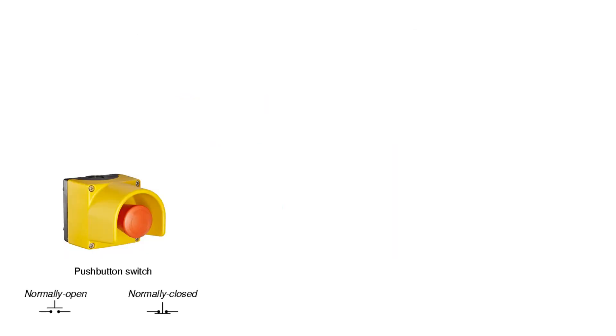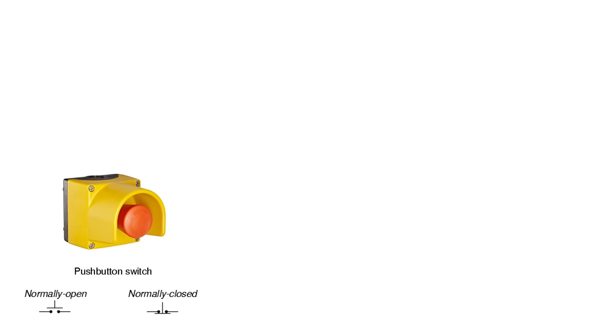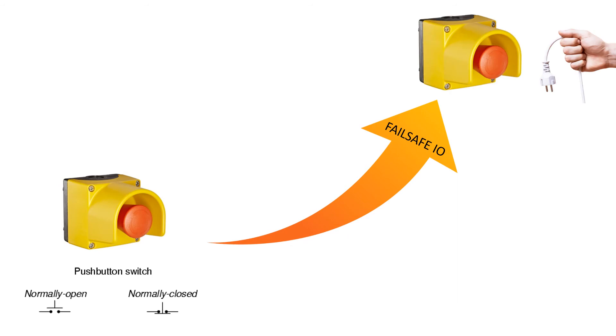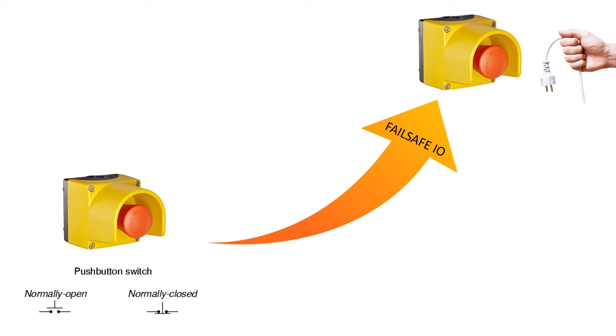Safety IO devices are typically wired in a normally closed contact arrangement. That means the contacts on the e-stop shown here are normally connected. The signal coming back is normally on until the button is pushed. The reason for this is so that if a wire gets loose or disconnected, the control system will shut down. Failsafe IO takes this to another level by periodically, within milliseconds, turning off the power to the e-stop and verifying that the signal coming back turns off as well.